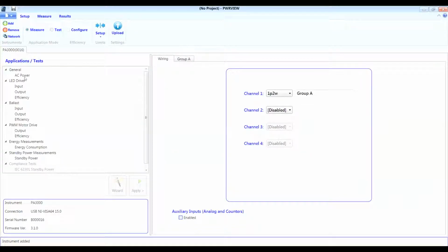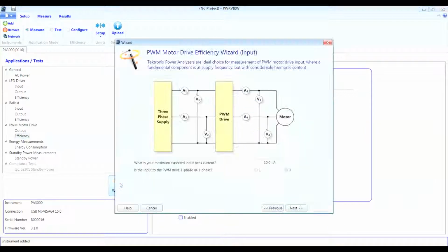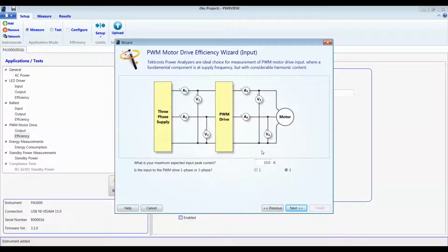Here on the setup page, we are going to select PWM motor drive efficiency on the left, and click on Wizard. The Wizard will help us with the wiring setup. We are connected in three-phase, three-wire configuration for input and output. With three-phase, three-wire, we just need 2 wattmeter channels on the power analyzer to accurately measure three phases. We have our three-phase input on the first two channels and three-phase output on the third and fourth channel.